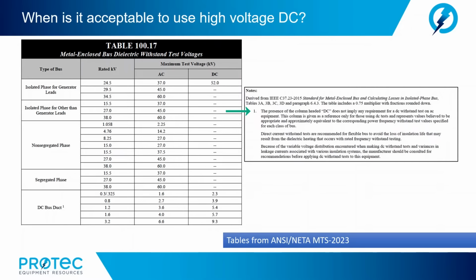In note number 1, the presence of the column headed DC does not imply any requirement for a DC withstand test on AC equipment. This column is given as a reference only for those using DC tests and represents values believed to be appropriate and approximately equivalent to the corresponding power frequency withstand test values specified for each class of bus. Direct current withstand tests are recommended for flexible bus to avoid the loss of insulation life that may result from dielectric heating that occurs with rated frequency withstand testing.